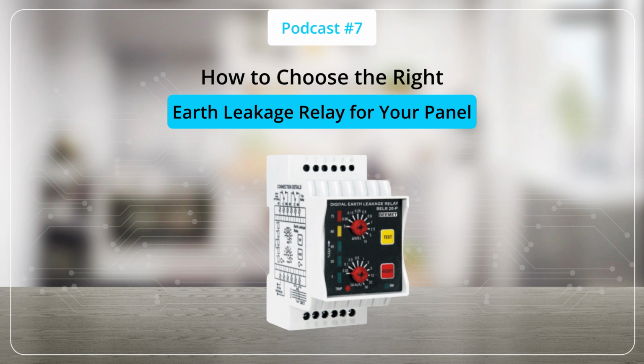Now let's look at the key factors that should be considered when selecting the right earth leakage relay for a panel. Choosing the right ELR requires an understanding of the load, system design, and protection objectives. The first factor is sensitivity, also known as trip current. This determines the leakage current level that will trigger the relay. For personnel protection, 30 milliamps is commonly used. For fire protection, settings between 100 and 300 milliamps are often selected, while industrial applications may require values up to 30 amps.